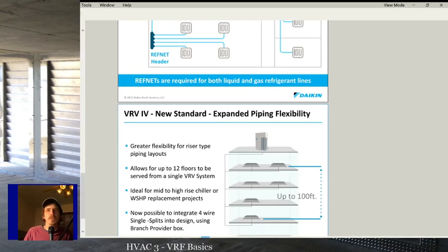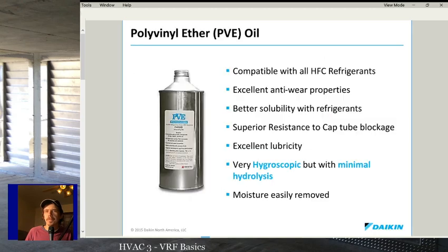Alright, the first thing about it is VRF and mini splits do not use the same oil as your typical 410A system. So if we're talking residential or commercial unitary systems, as a lot of people like to call them these days, basically standard systems, you know, RTUs, split systems, things of that nature, most of our 410A systems use POE oil. Alright, mini splits and VRF tends to use PVE oil. There's some differences between POE and PVE, and honestly I think the PVE oil is the better of the two, although I'm not an engineer and I can't tell you which one is actually better from a manufacturer's perspective, but I believe it would still be the PVE oil, the one they use in the mini splits and stuff.